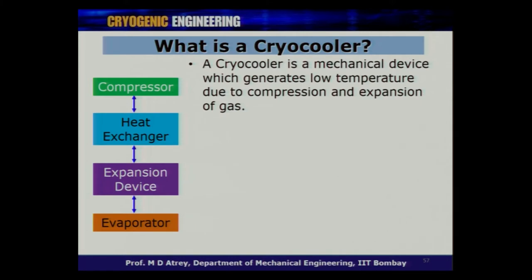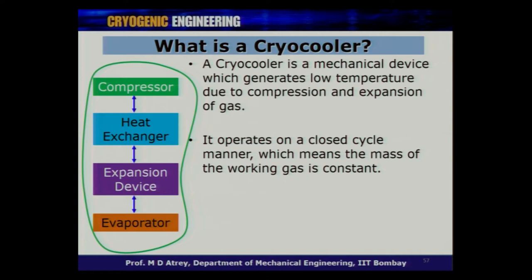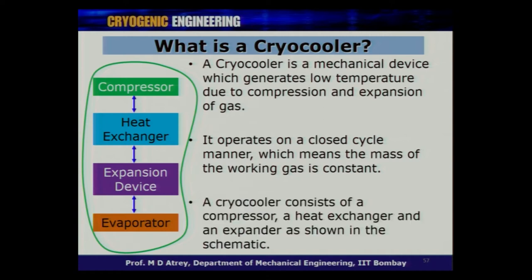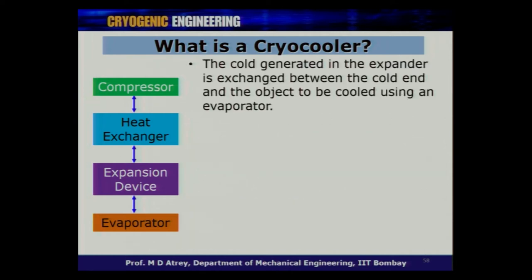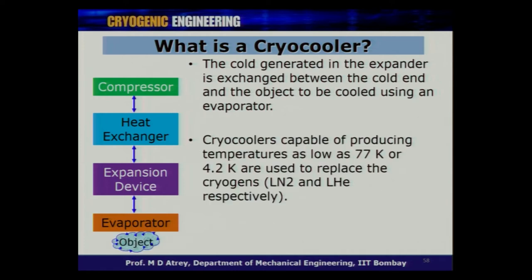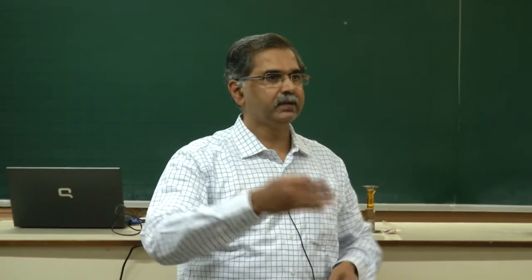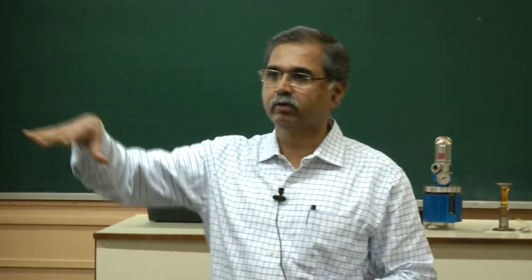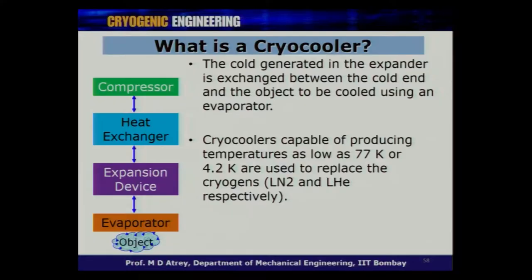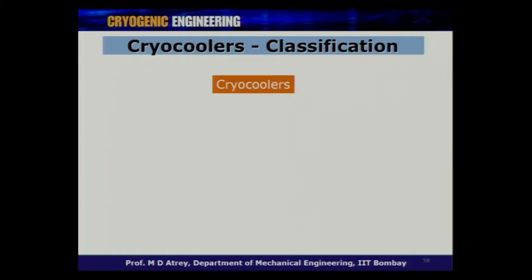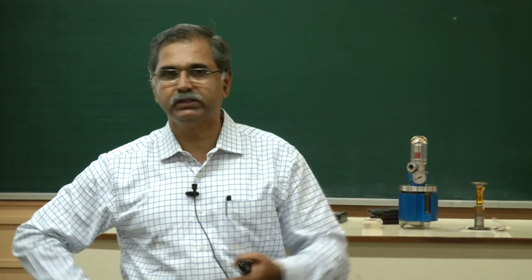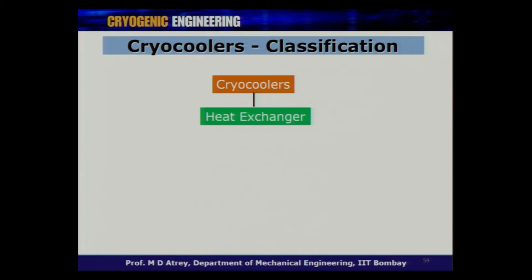In a cryocooler, electronics need to be cooled. The object to be cooled works in a closed-cycle manner, just like a domestic refrigerator. A cryocooler consists of a compressor, heat exchanger, and expander. The cold generated in the expander cools the object — which could be anything generating heat. If the electronics are not cooled, you get signal problems and a lot of noise. The object can be cooled to 80 or 90 Kelvin depending on requirements. These cryocoolers are classified based on the kind of heat exchanger they use.